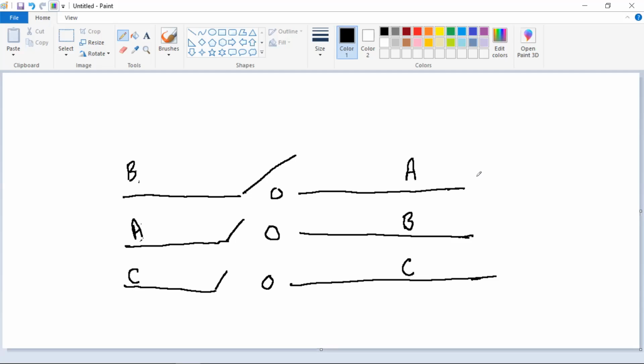What would happen in this case right now if I've got breaker C over here and breaker A, and I'm already set up and through the process of switching? What would happen if I close the switch on the top, the B and A circuit, B and A phases? I'm gonna trip the breakers, isn't it? It's going to trip both the breakers out. Essentially what you're doing right there is creating a phase-to-phase fault.